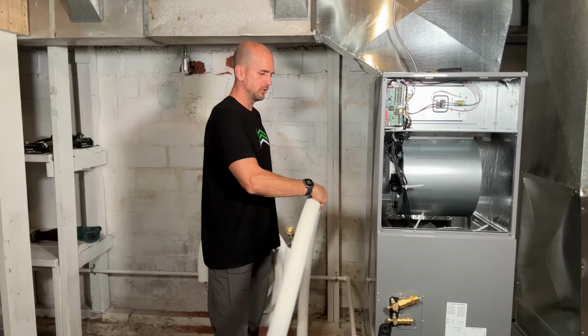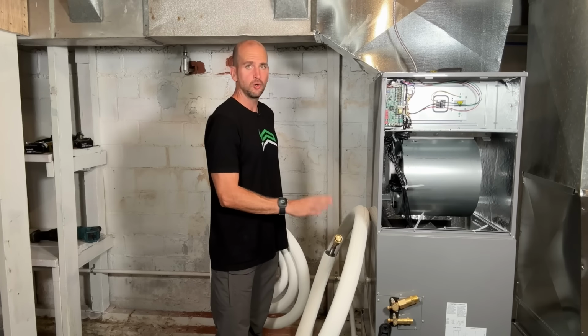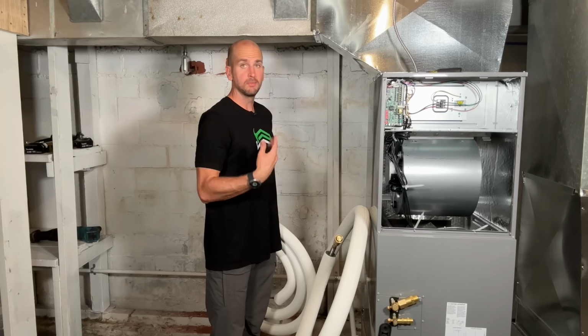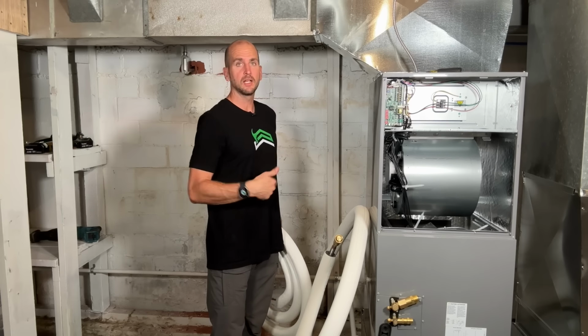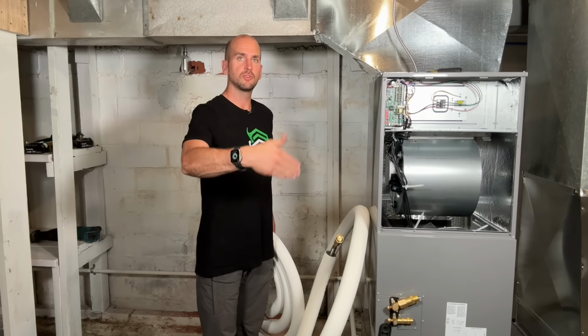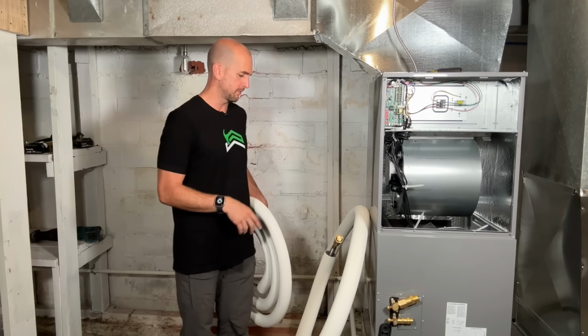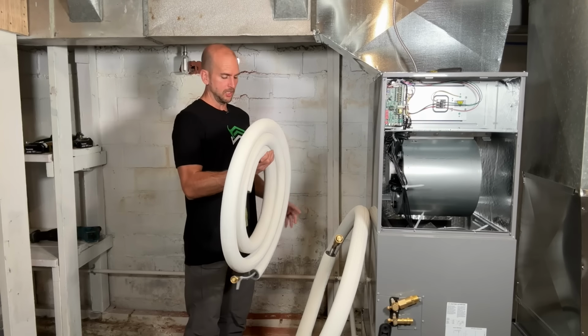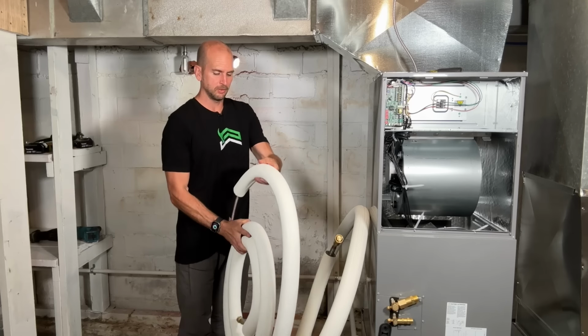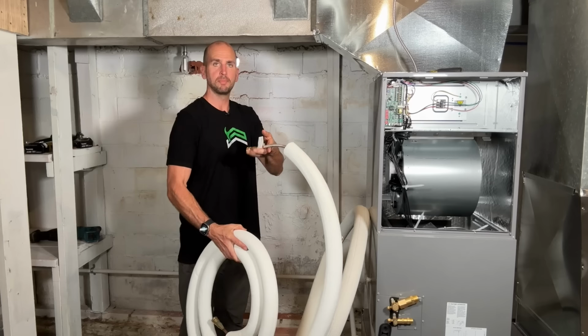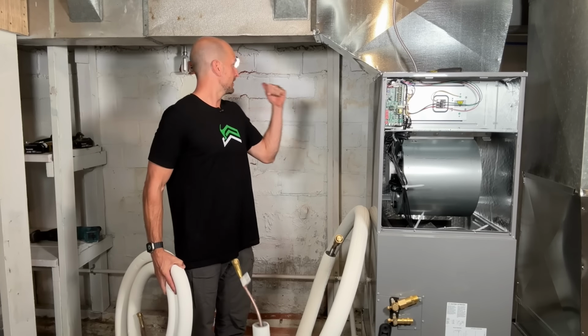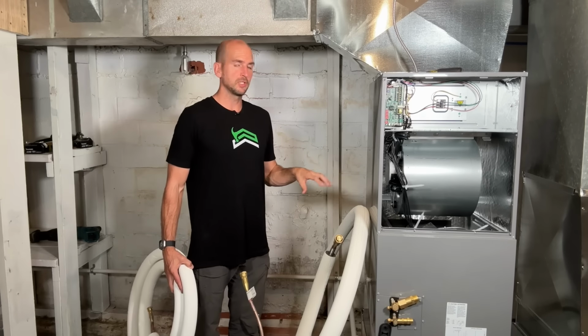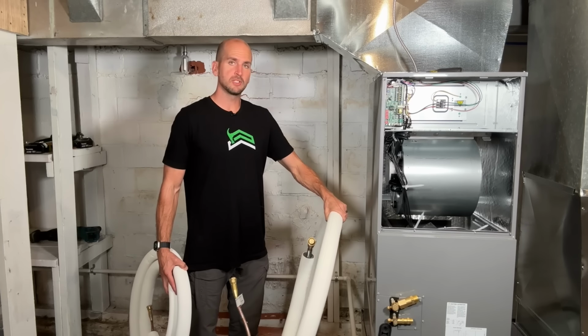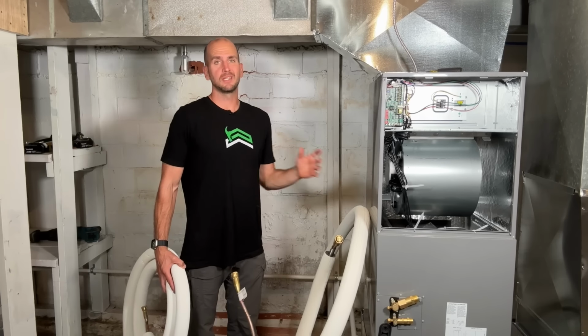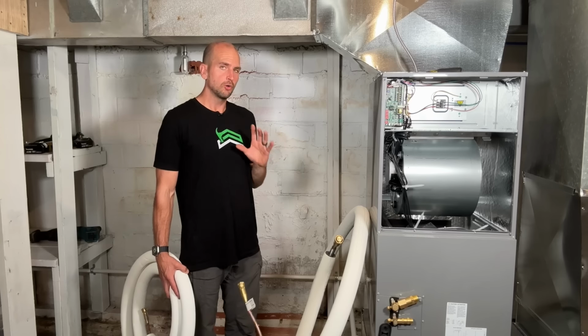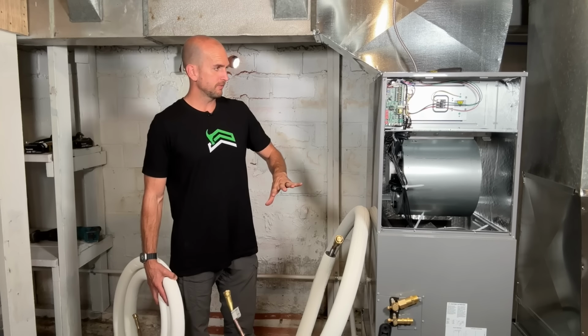All right, so we have our two different lines, and these No-Vac or no vacuum lines come in set lengths. So 15 feet is what I got. That's about the shortest you can get. And then it's 5-foot increments from there, depending on your application. So you need to unwind these. They are gonna be a little bit rigid. Obviously the smaller line's easier to bend than the larger line. And then this small hole is gonna be a little tight for both of these going through. So I'm gonna really have to squish down this insulation to get it through the hole, but then that will just leave less for me to seal up. So hopefully I can get that through. So now I'm gonna kind of fight with these lines.